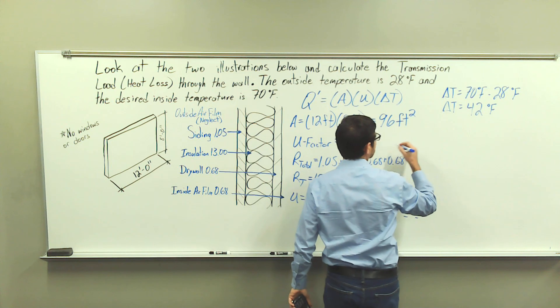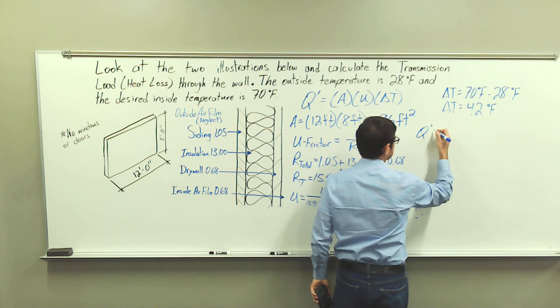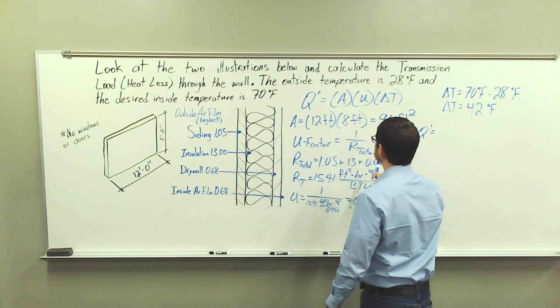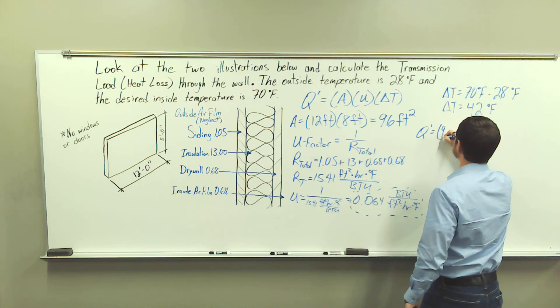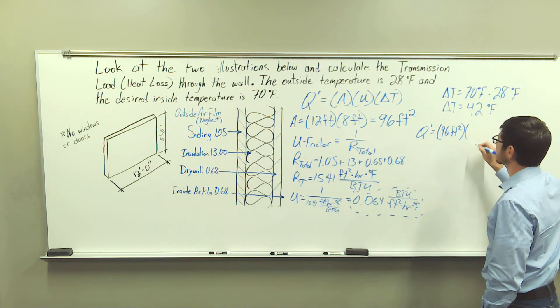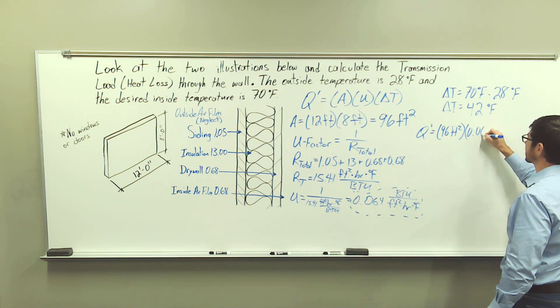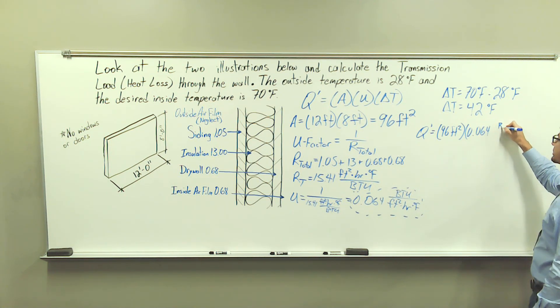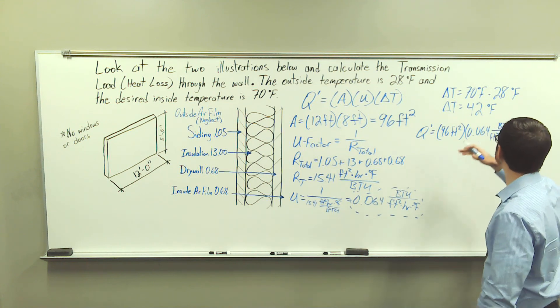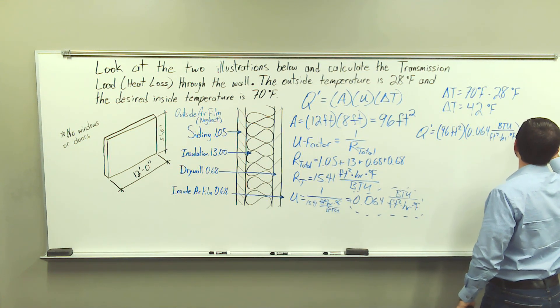So what we're going to do, Q prime, my area is 96 square feet. My U factor is going to be 0.064, and we have units of British thermal unit per foot squared hour degrees Fahrenheit, multiplied by our temperature difference, which is going to be 42 degrees Fahrenheit.